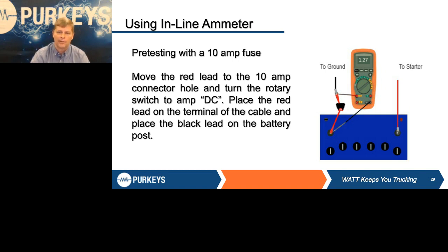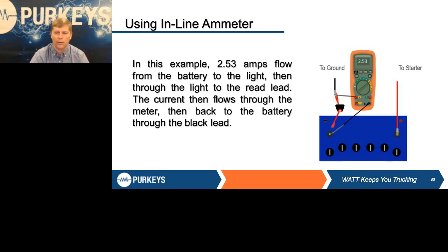Half that current goes through the fuse holder and half goes through my meter. So once I pull that fuse holder off, it all has to go through my meter, and I'll get a much more accurate reading of what the load truly is.